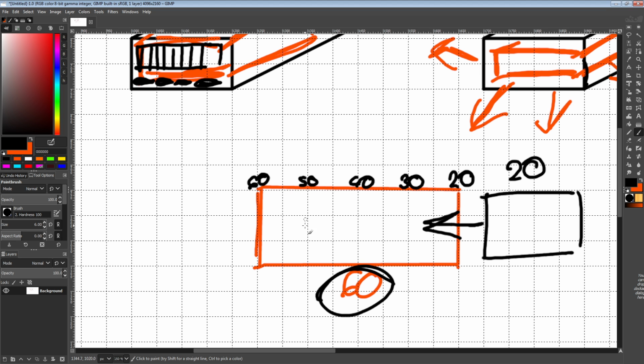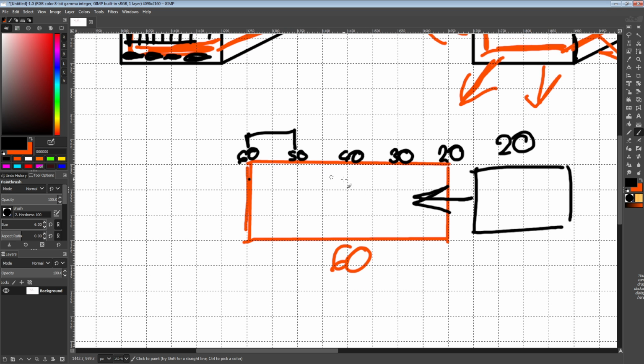Do you know what this tells us? We need more airflow, because in this last stretch, the thermal transfer over this surface area is terrible — the temperature difference between the fin stack and the air here is like 5 degrees on average. We'll pretend it's that simple, though it's not. Whereas in the first part of the fin stack, the temperature difference between the air and the fin stack is more like 35 degrees on average — much bigger, so thermal transfer there is much better than over here.